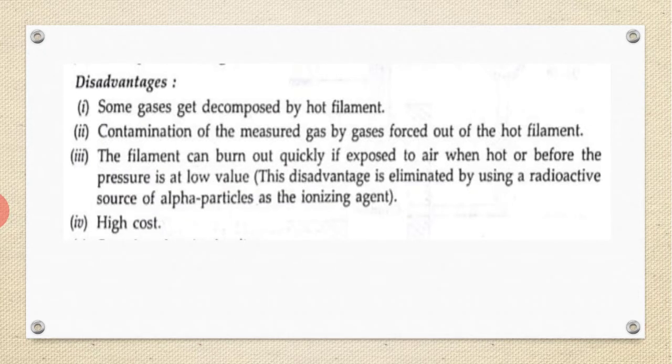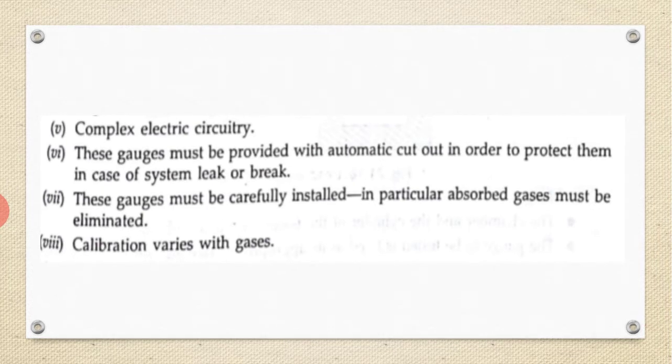Some of the disadvantages mentioned here: some gases get decomposed by the hot filament. Contamination of the measured gas by gas forced out of the hot filament. The filament can be burnt out quickly if exposed to air when hot or before the pressure is at a low value. High cost. Complex electric circuitry.